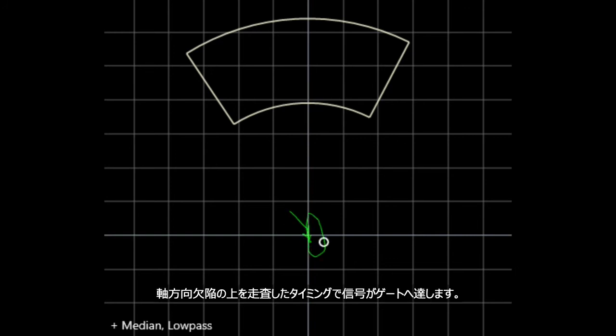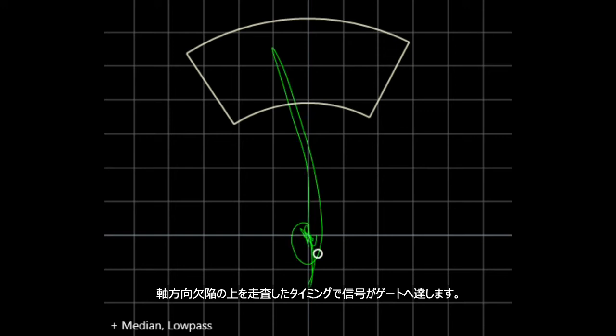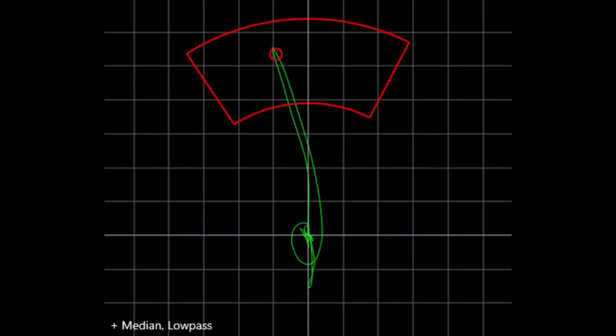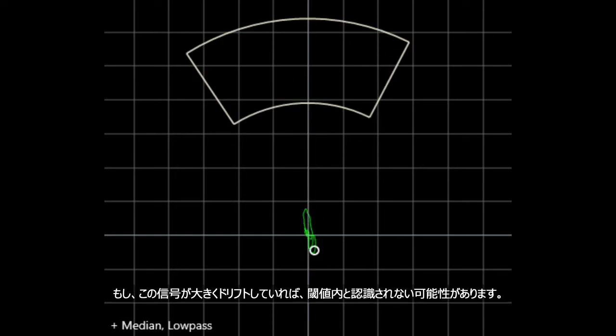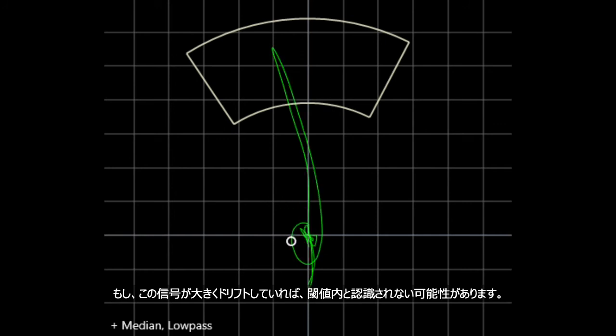I will now go over an axial flaw and the signal hits the alarm threshold. If there were significant drift, the flaw signal may not hit the alarm threshold.